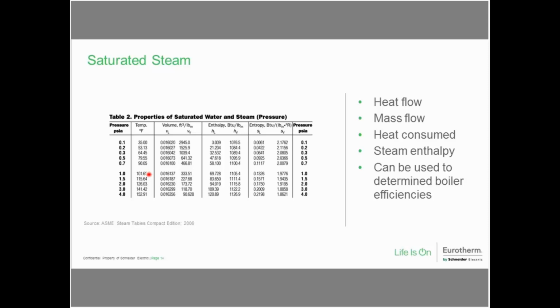The application blocks allow you to use these values to calculate things like heat flow, mass flow, heat consumed, and enthalpy. Putting those together with some of the other math and logic function blocks in the nanodac, you can start to determine efficiencies like boiler efficiency—how much energy am I putting into the system versus how much am I actually getting out?